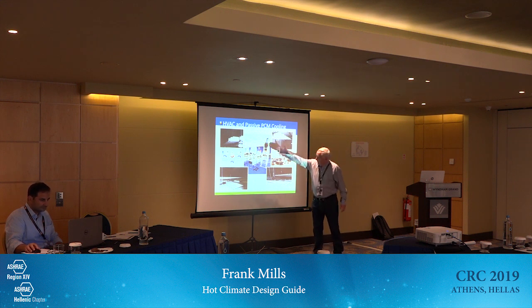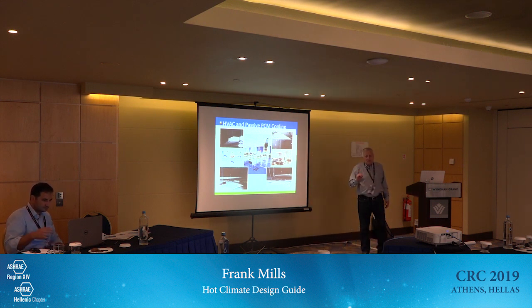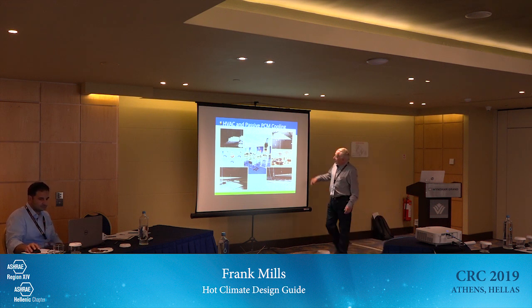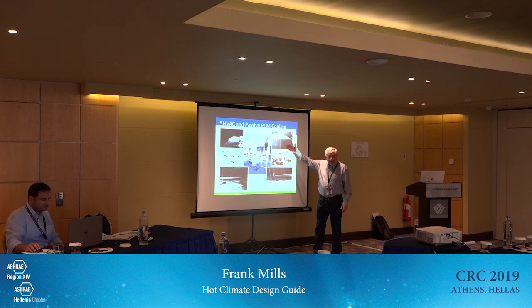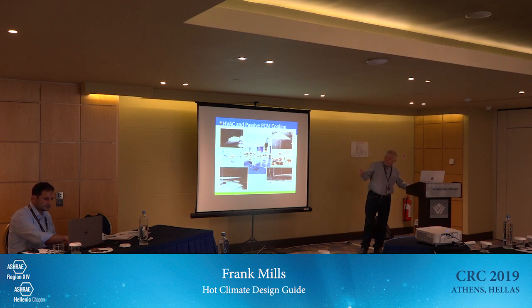So we did it. We put it in the rooms, all the rooms that were necessary, and it's worked great. It's fantastic. It does work. So I call it free air conditioning. It works great because at night we flush these rooms with cool air, and they refreeze, and the next day they take 7 or 8 hours in hot weather, obviously, to re-melt. So there's an example of phase change material cooling in a classroom situation. The biggest room I did was a seminar room that had 120 people in it, so it's quite a big load.